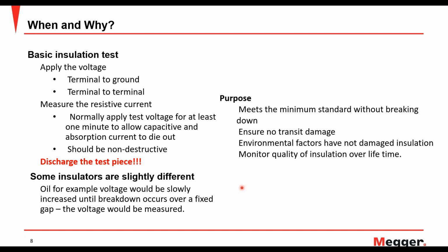And then you slowly, gradually increase the voltage until a flashover or breakdown happens, and then it drops down. So that insulator is slightly different from your normal insulation test. What's your purpose? Meet the minimum standard without breaking down. So definitely that's your main goal, that it holds the voltage without leaking to anything else.